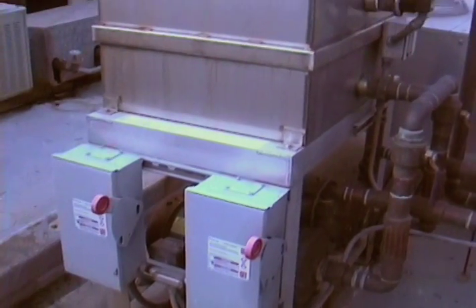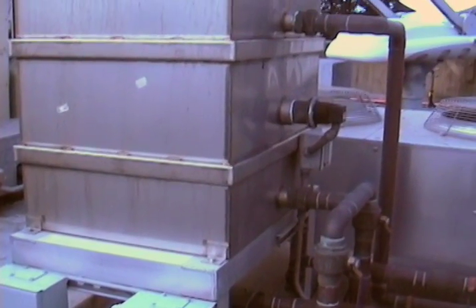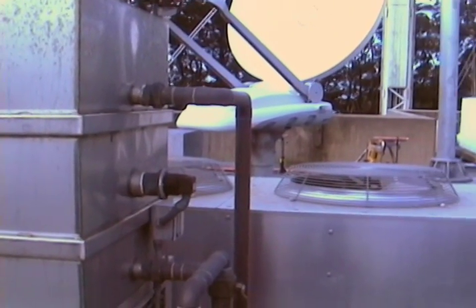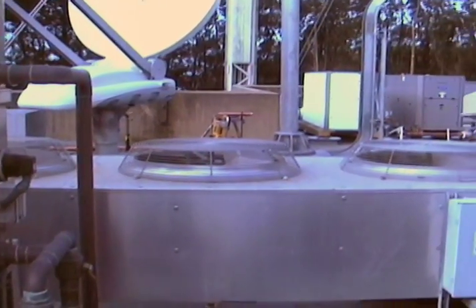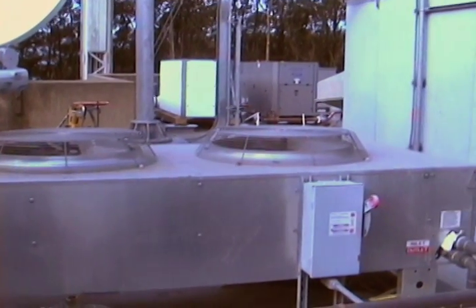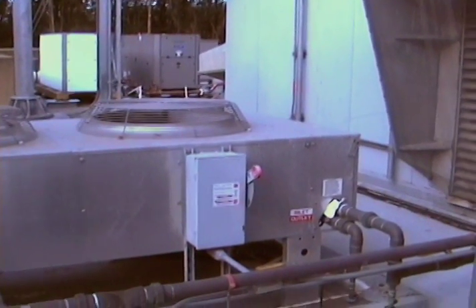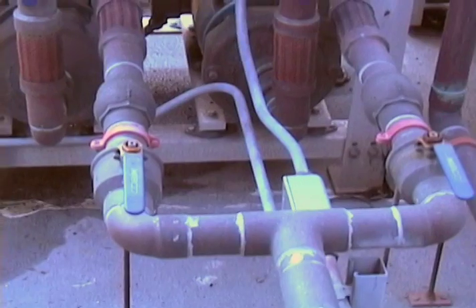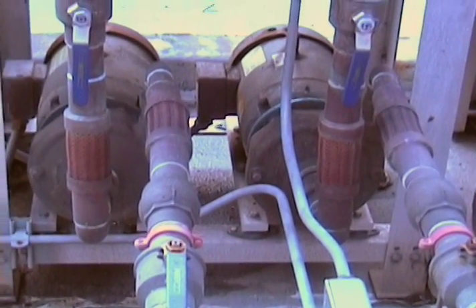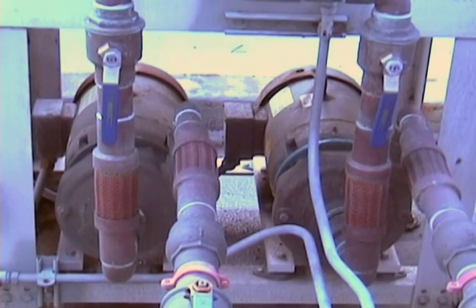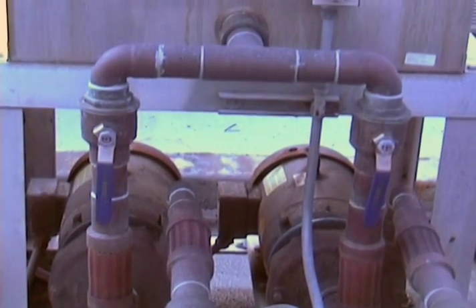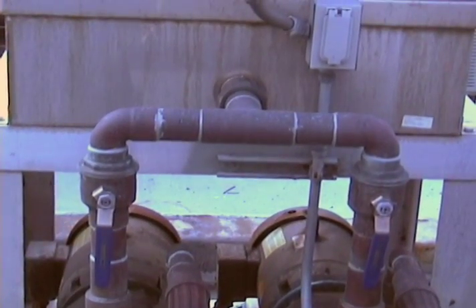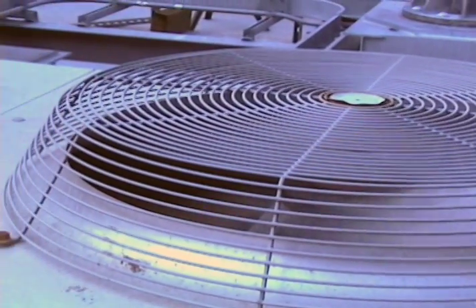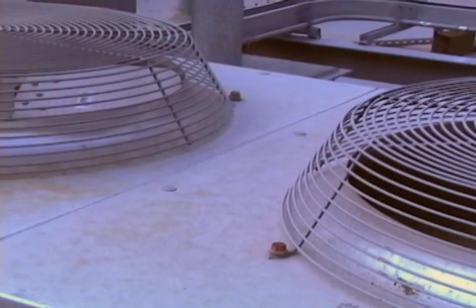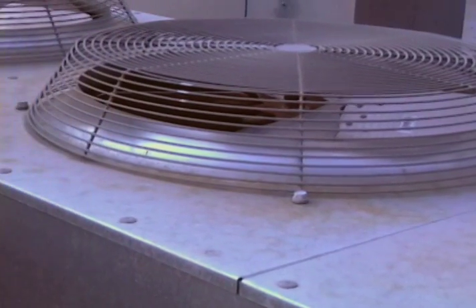The heat exchanger on the roof utilizes a tank to hold the coolant and a radiator with several fans to cool it before it returns to the transmitter. Most systems use 2 water pumps to avoid a shutdown in case one fails. The fans turn on as needed for the amount of cooling required.